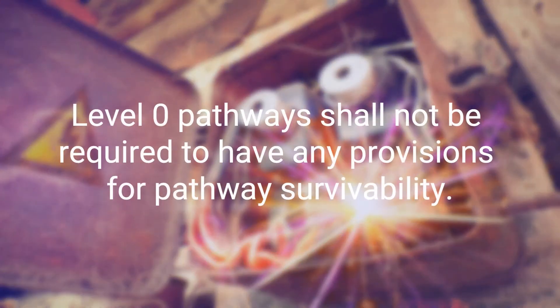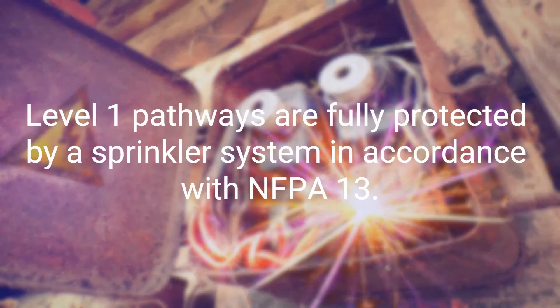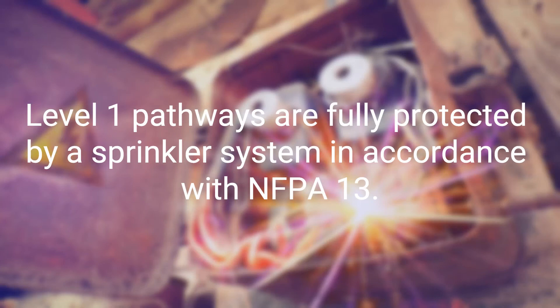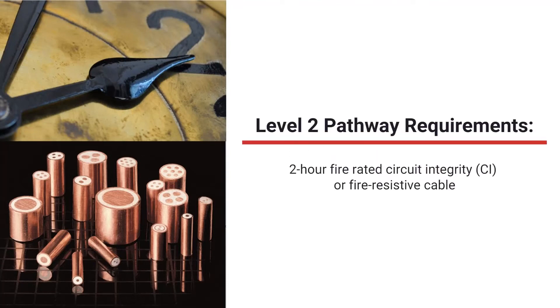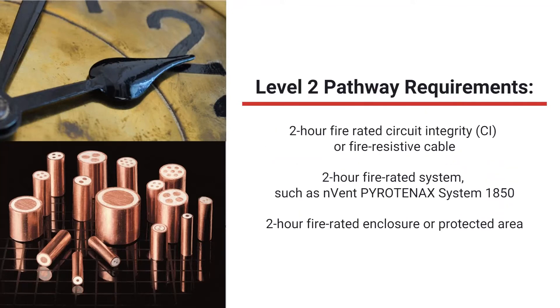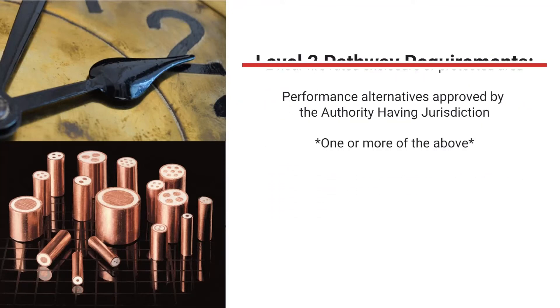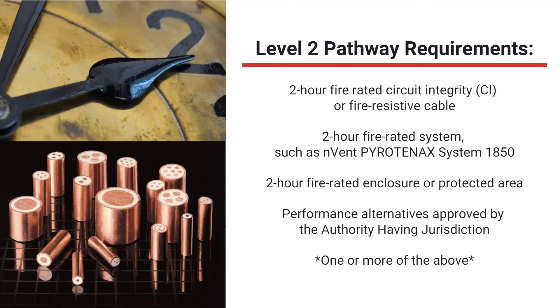Level 0 pathways shall not be required to have any provision for pathway survivability. Level 1 pathways are fully protected by a sprinkler system in accordance with NFPA 13. Level 2 pathway survivability consists of one or more of the following: a 2-hour fire rated circuit integrity (CI) or fire resistive cable, a 2-hour fire rated system such as nVent PYROTENAX System 1850, a 2-hour fire rated enclosure or protected area, or a performance alternative approved by the local authority having jurisdiction.